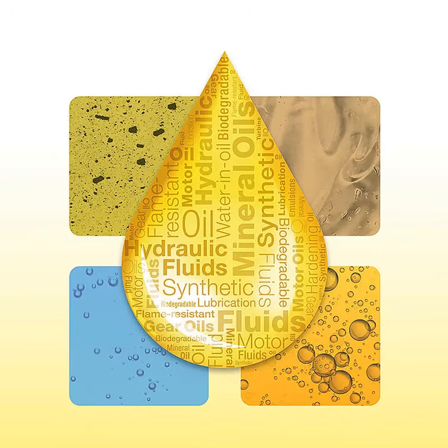Other fluids can also become contaminants. Mixing the wrong lubricants, whether intentionally or accidentally, can create problems depending on the fluids involved. Finally, we have gaseous contamination. Hydraulic fluids naturally contain some dissolved air. The air itself isn't necessarily the biggest concern, but the oxygen it contains contributes to oxidation of the lubricant.